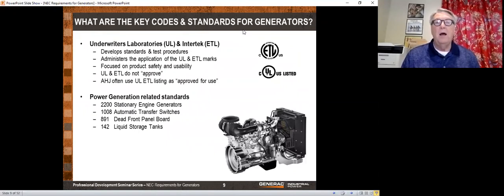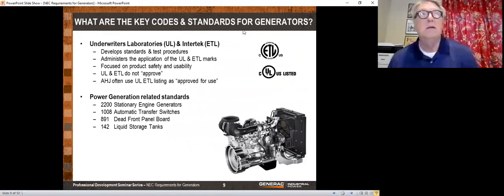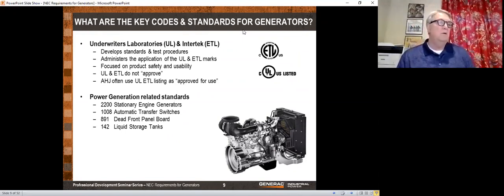Underwriters Laboratories, when I got into this business, you didn't see many generators with a UL label. And they're still, like motors typically are not UL listed, but generators are, and these days you must have a UL sticker on your generator. If you don't, there's a good chance that the authority having jurisdiction, in other words, the fire marshal or their local inspector, is not going to accept that.